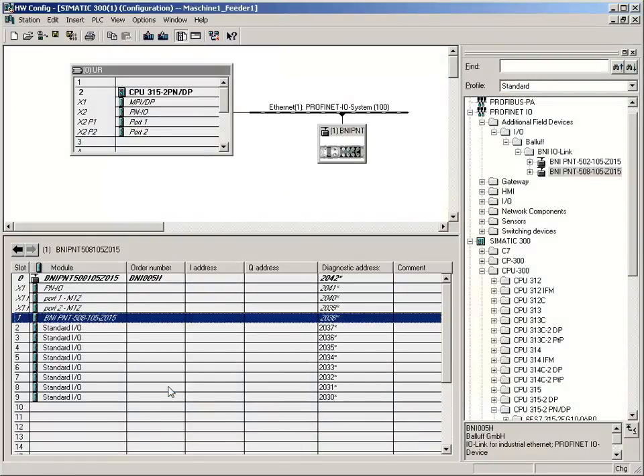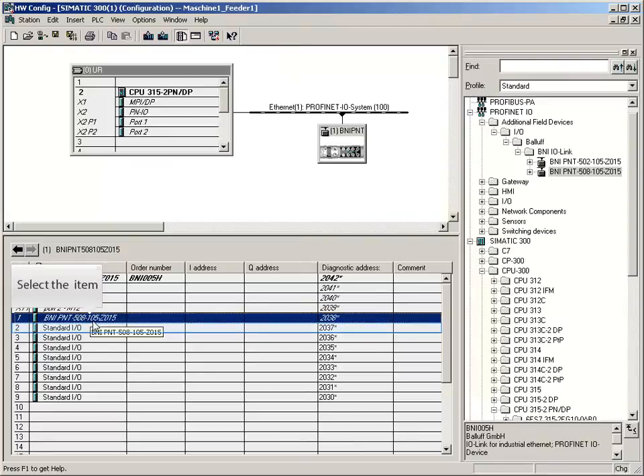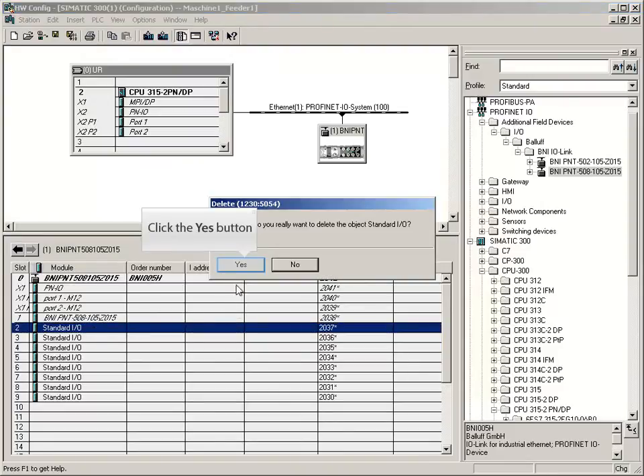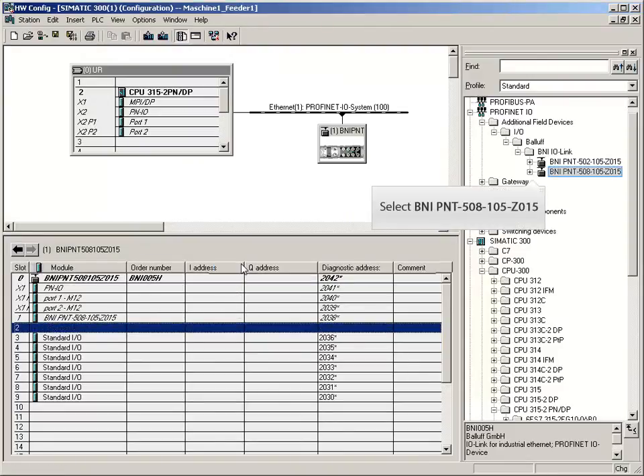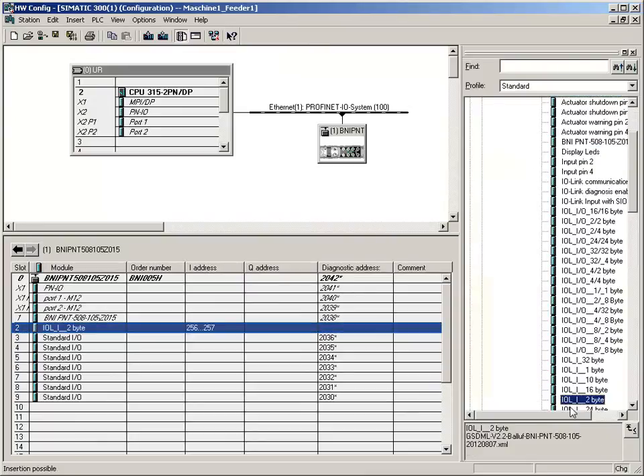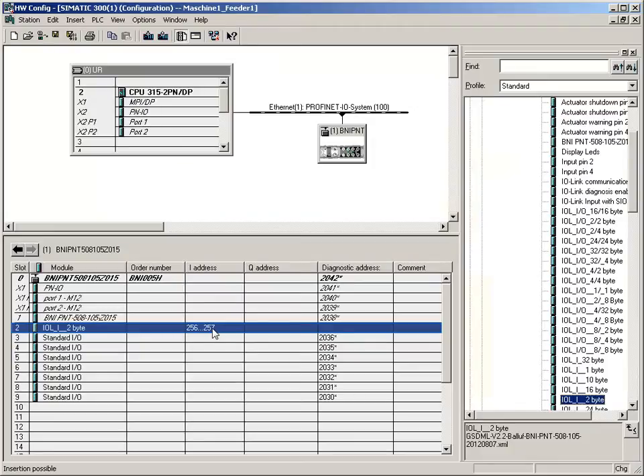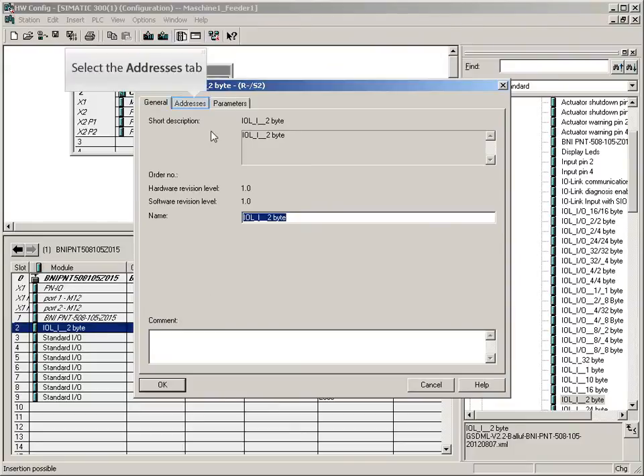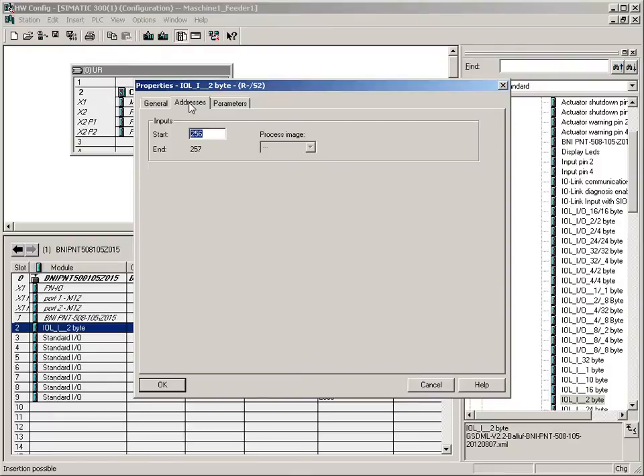Next step is to configure the IO link ports according to the connected IO link devices. The current entry must be deleted. Open the directory of modules and drag the module with 2 input bytes to port 0, because according to the documentation, connected sensor hub 2 input bytes are needed. Now the addresses of process data have to be assigned. Therefore click on the tab addresses. The system suggestion will be replaced by address 0.